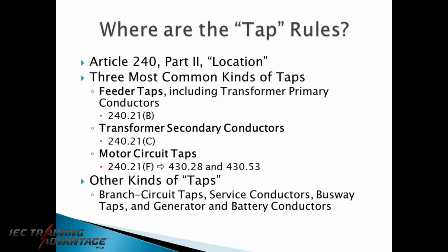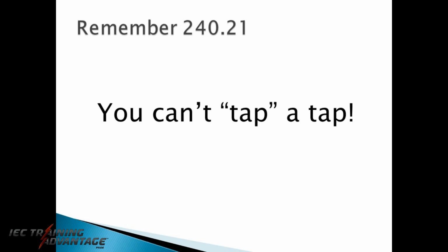We are going to focus in this video on feeder taps and their rules. Now, before we get into all the little rules, we are going to remember 240.21. Should be pretty easy to understand and remember. You can't tap a tap. So let's get into the details of feeder tap rules.